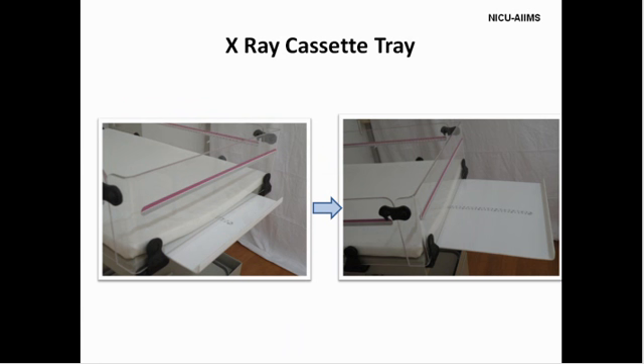Many warmers have an X-ray cassette tray that is located beneath the bed. This tray can be pulled out for insertion of X-ray cassettes, thereby allowing us to take X-rays without moving the sick baby. The markings located along this X-ray plate allow for easy location of the cassette in the X-ray tray relative to the position of the baby on the warmer bed. Remember, the quality of X-ray taken by this method may not be optimal in all clinical scenarios.